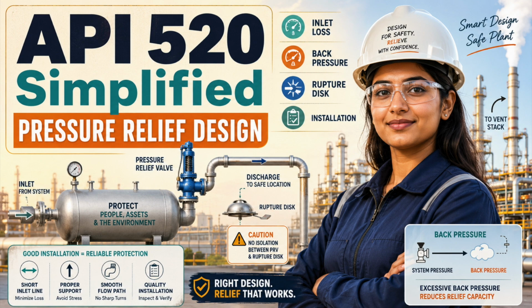A correct calculation connected to bad piping is still a bad design. A balanced valve with a blocked vent is still a bad design. A rupture disc with the wrong temperature basis is still a bad design. A pilot-operated valve in fouling service without protection is still a bad design. A redundant arrangement that can be defeated by one valve position is not true redundancy.